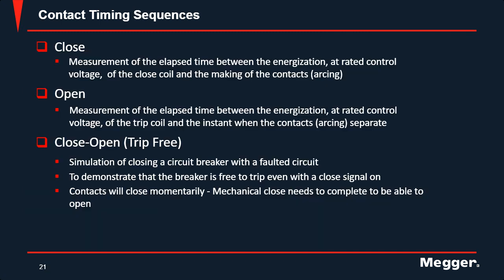So we're doing our timing test. There are 5 main sequences that you can do. The majority of people only end up doing 3 of them. The other 2 are more situational, based off how your protection relay is set up to work. So the 3 main ones are your close, your open, and your close open. Obviously, the close measurement is the time elapsed between energization, getting that signal to close to the close coil, and then the contact actually making contact. And then your open command is going to be the exact opposite. When your signal gets to your trip coil, your test step will start your timer. And once those contacts are fully open and no longer stationary, it will stop the timer. Once the signal gets to your trip coil and the arc is extinguished, that is when the timing stops.